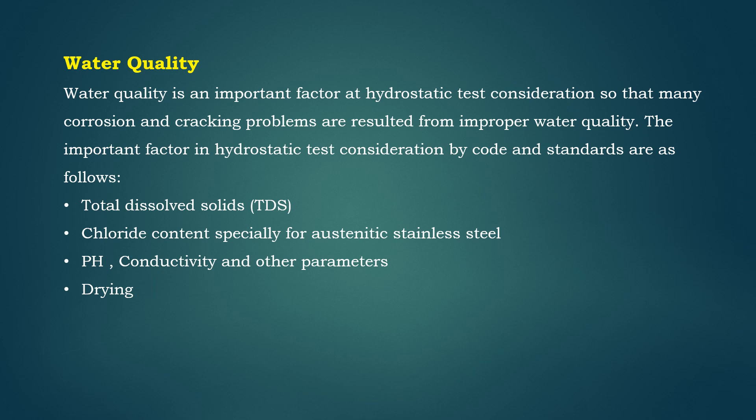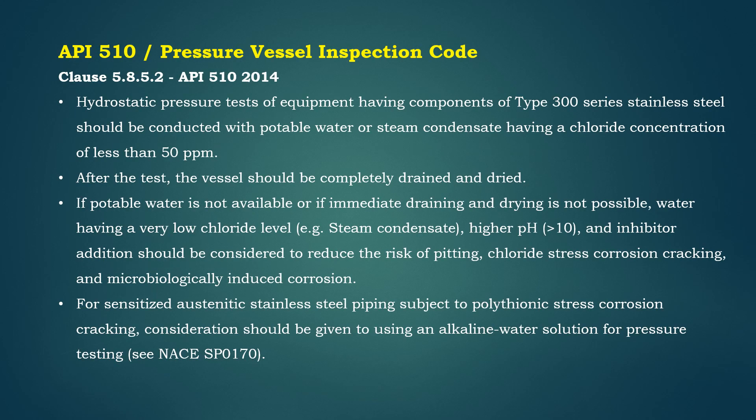During hydrostatic pressure tests of equipment having components of Type 300 series stainless steel, tests should be conducted with potable water or steam condensate having a chloride concentration of less than 50 ppm. After the test, the vessel should be completely drained and dried. The inspector should verify that the specified water quality is used and that the vessel has been drained and dried.